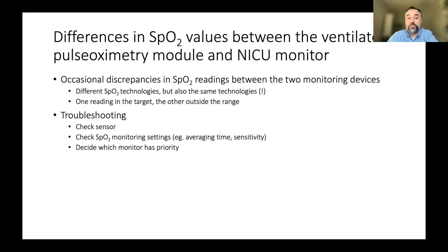One of the problems may be that there are different technologies, SpO2 measurement technologies used, but we also saw it with the same technologies. So one reading can be in the target range, the other one outside the target range. For sure, you should make sure to troubleshoot, you should make sure that the sensor is properly placed, that it's working properly. Also check the settings, so make sure that the same settings you have on the main monitor in your NICU and also on the SpO2 settings on the ventilator, and also decide which monitor has got the priority.